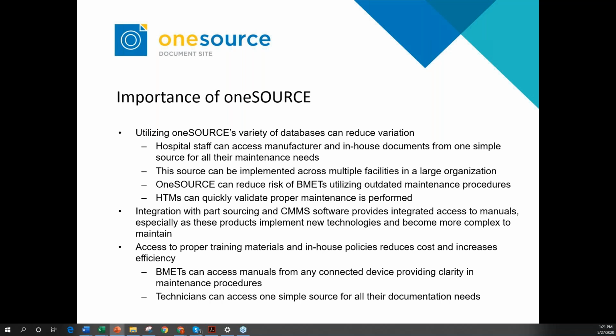oneSOURCE obviously reduces the risks of BMETs utilizing outdated maintenance procedures. Sometimes you might need to do a preventative maintenance inspection and you have a manual in your shop that you're just going to use, but you're not checking to make sure that a new revision hasn't changed in the manual, or a new test hasn't been revised to perform. So this is going to reduce the risk of that, make sure you're compliant, and improve patient safety. Because you can verify that you're doing the proper maintenance procedures, and that leads to HTMs quickly being able to validate proper maintenance.